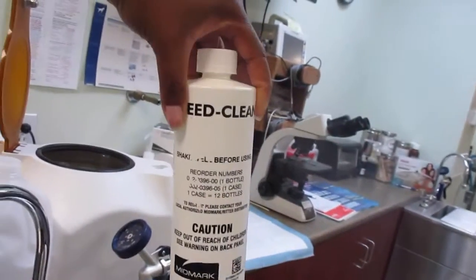So whoever runs the autoclave is making sure that they don't see any of those things, especially the steam escaping when it's actually sterilizing. And weekly, we want to drain the water inside, which is the distilled water, and replace it with new distilled water. And we're going to go ahead and wipe the racks down with distilled water and a speed cleaner, which is this right here. And wipe all the racks down, take the rack out and wipe that down as well. So yeah, and then we'll replace that back.